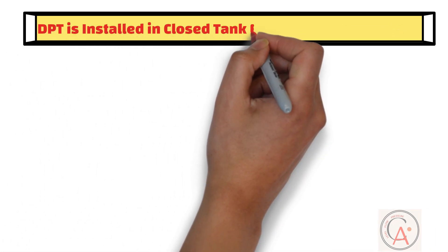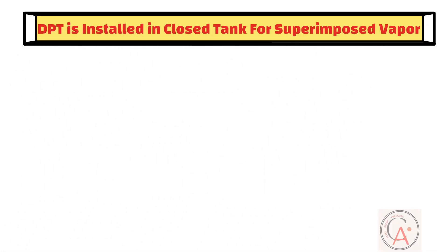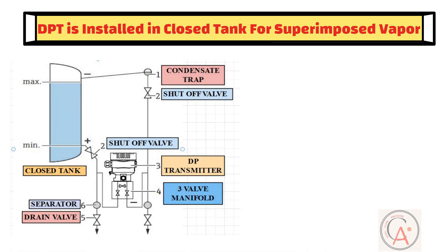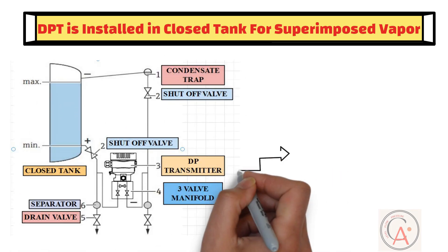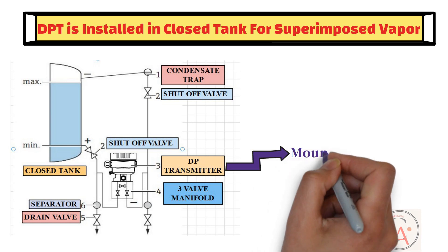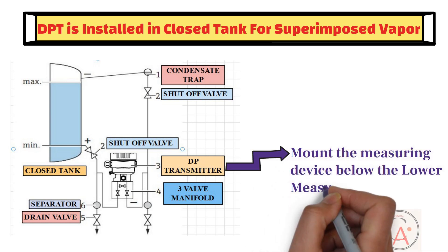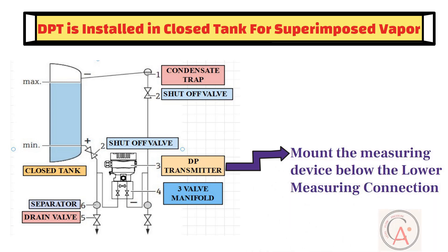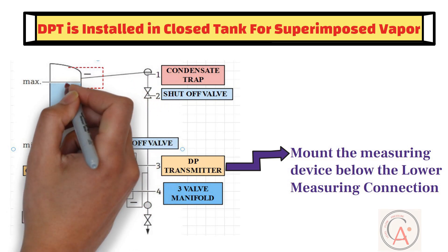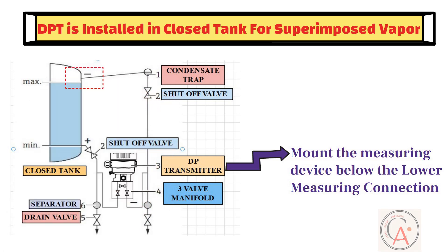Let's take the third scenario, when a DP transmitter is installed to measure level in a closed tank with superimposed vapor. As you can see from the diagram, in this condition, mount the measuring device below the lower measuring connection so that the impulse lines are always filled with liquid. The low pressure side needs to be connected above the maximum level. The purpose of the condensate trap is to ensure constant pressure on the low pressure side.